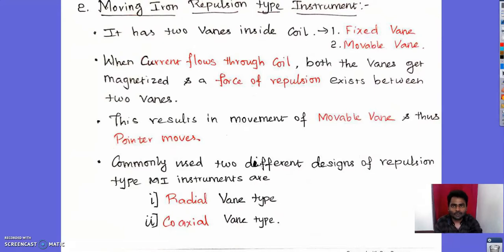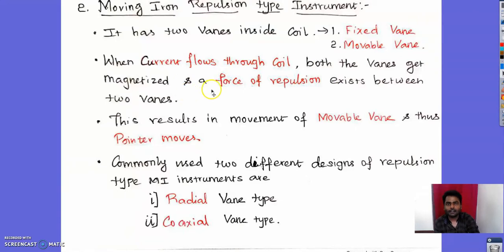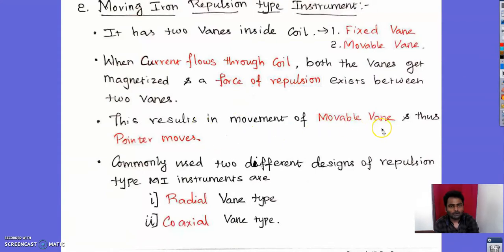The repulsion type moving iron instrument has two vanes: one fixed vane and one movable vane. When current flows through the coil both vanes get magnetized. Since both are magnetized with the same polarity, a repulsion force exists between them, causing the movable vane to move and deflect the pointer. Unlike the attraction type, here the pointer moves due to repulsion force.